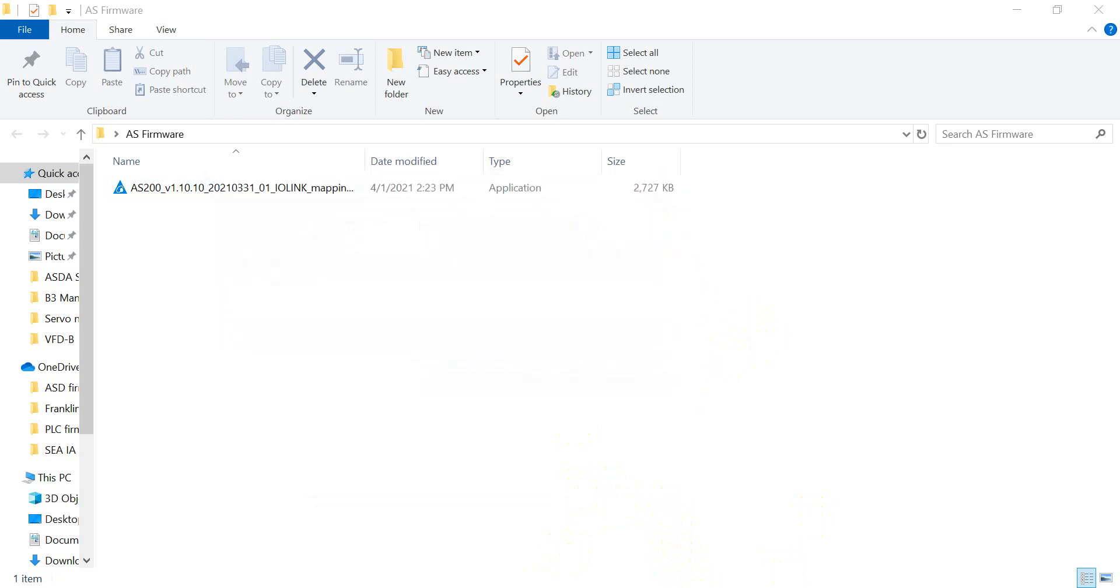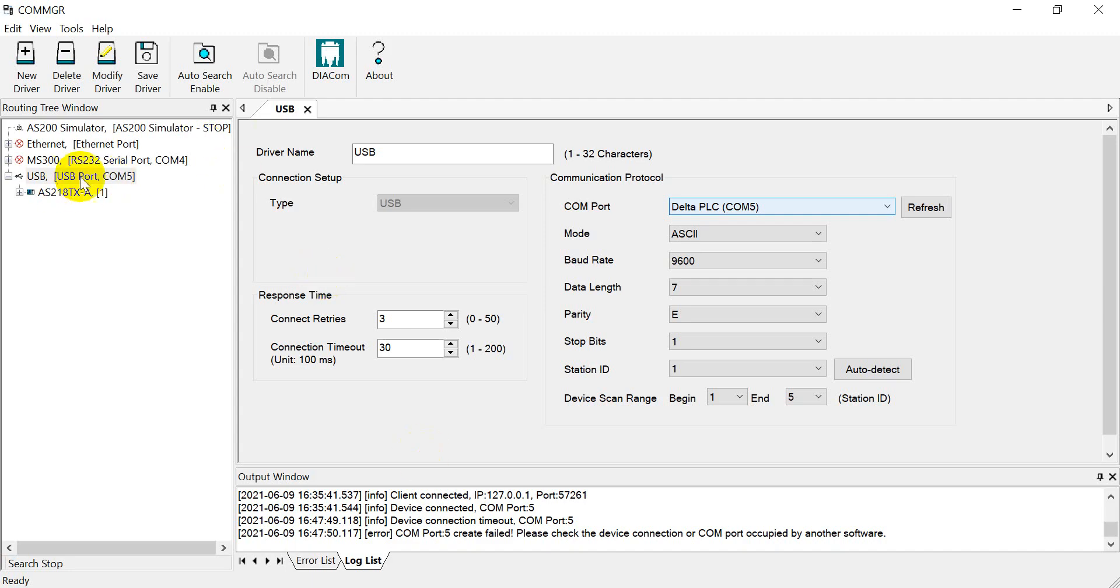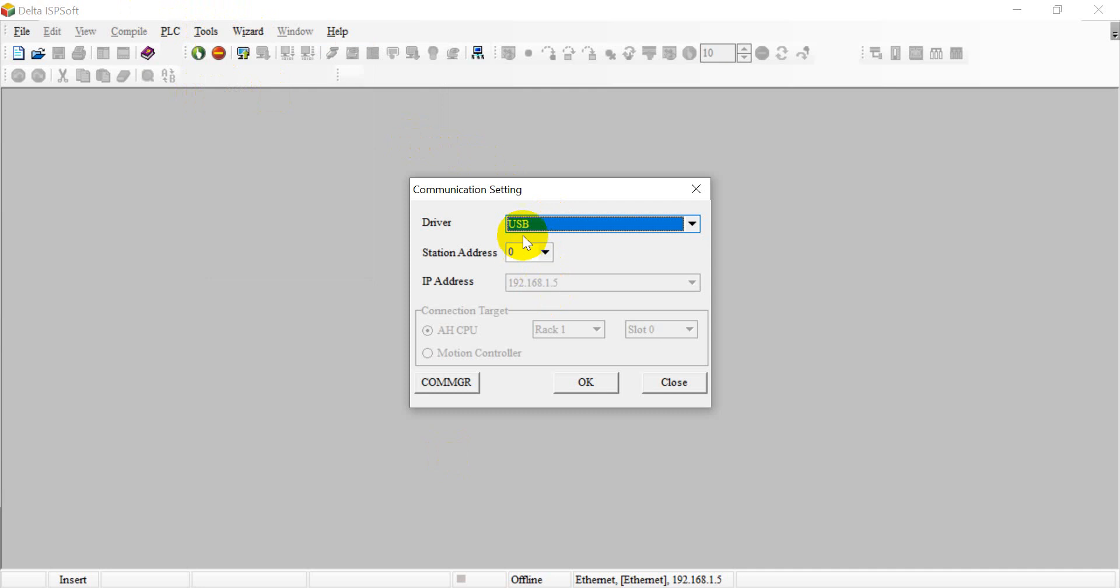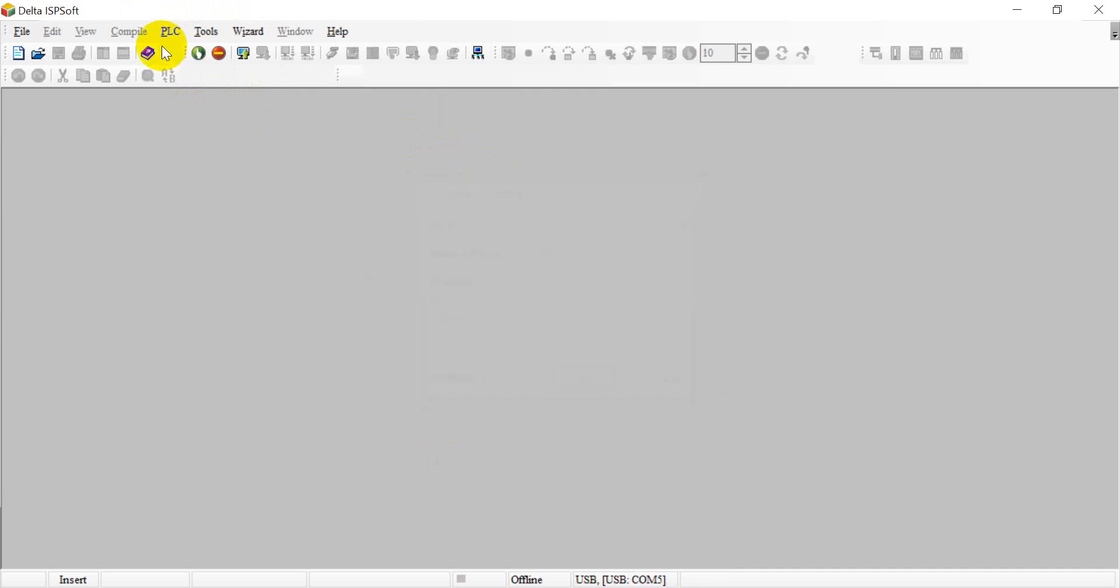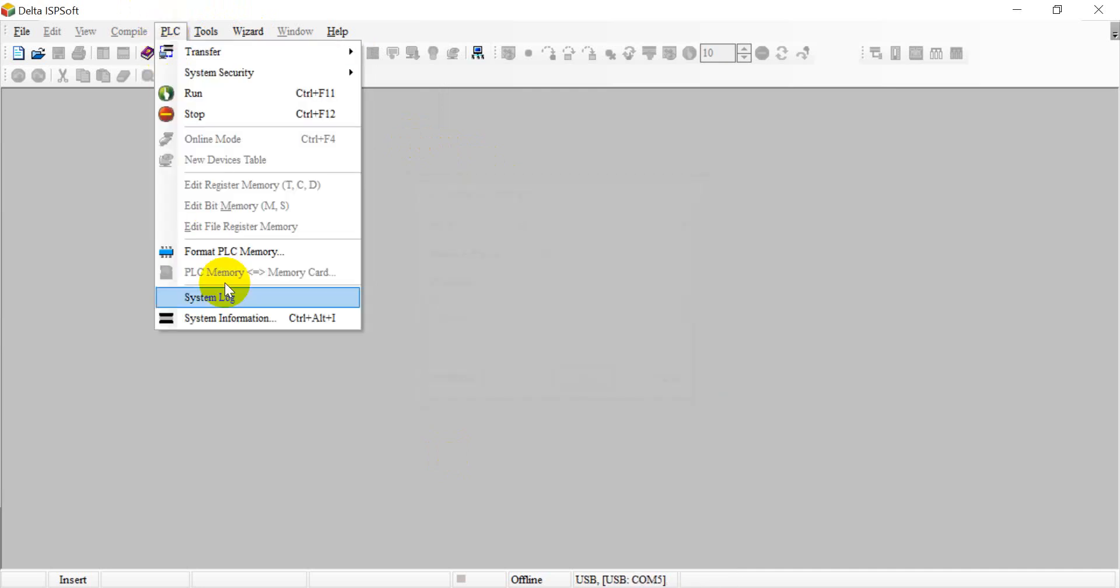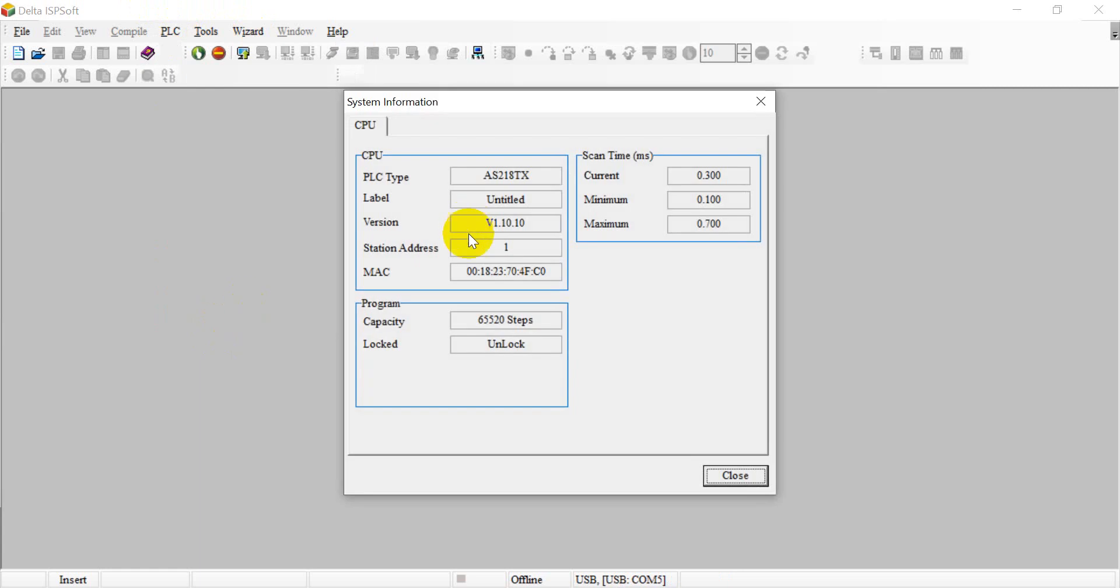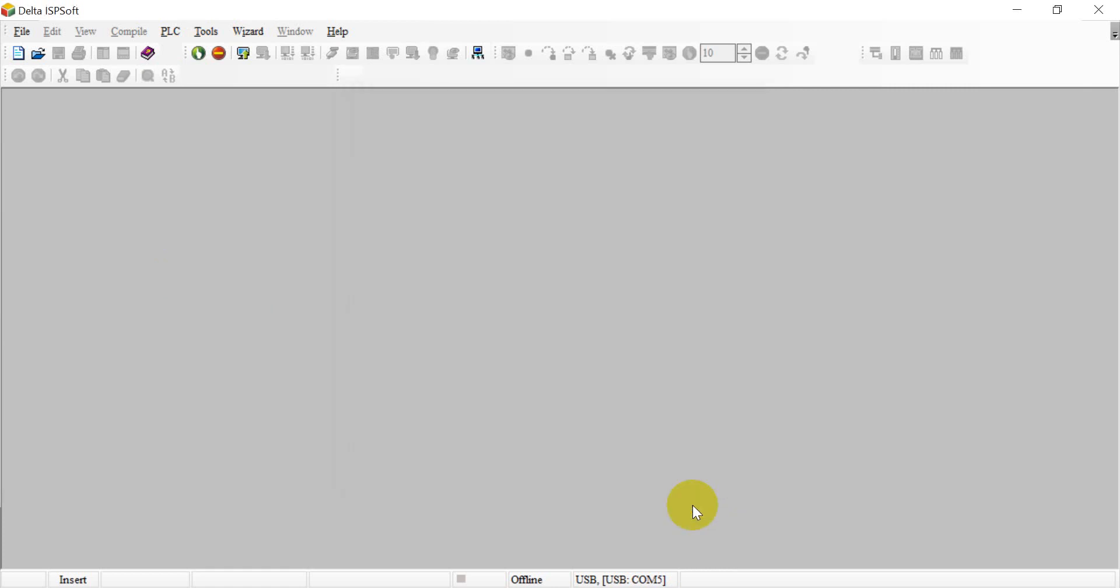Then we can go back to the ISPSoft. As you remember here, we should use the USB. Because now we link to PLC through USB. So here we select USB cable. Then we can open the ISPSoft, set the communication setting, and select USB interface. And again, then we go to PLC and select system information. So you can see now the firmware version upgraded to version 1.10.10. Okay, this is the first method.